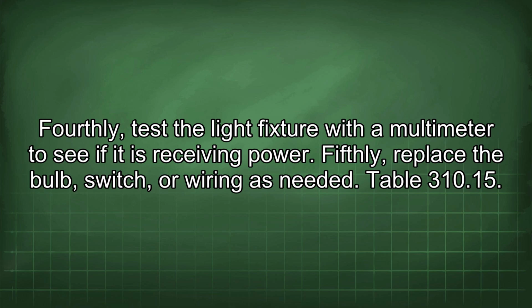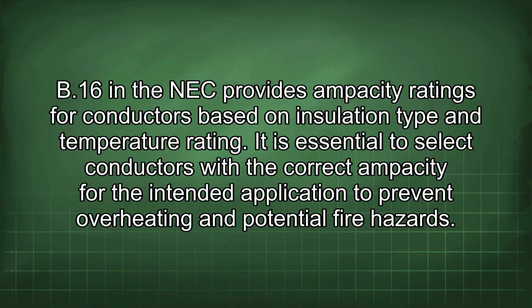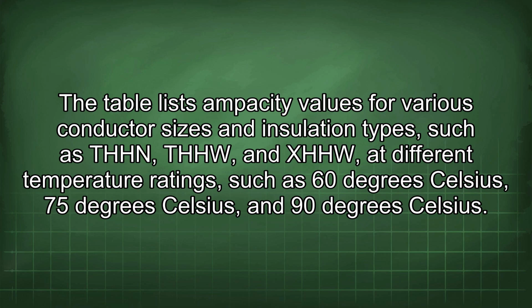Table 310.15(B)(16) in the NEC provides ampacity ratings for conductors based on insulation type and temperature rating. It is essential to select conductors with the correct ampacity for the intended application to prevent overheating and potential fire hazards. The table lists ampacity values for various conductor sizes and insulation types, such as THHN, THHW, and XHHW, at different temperature ratings, such as 60 degrees Celsius, 75 degrees Celsius, and 90 degrees Celsius.